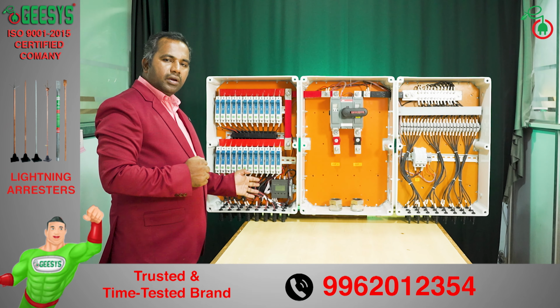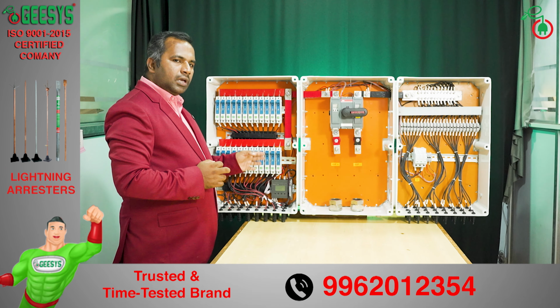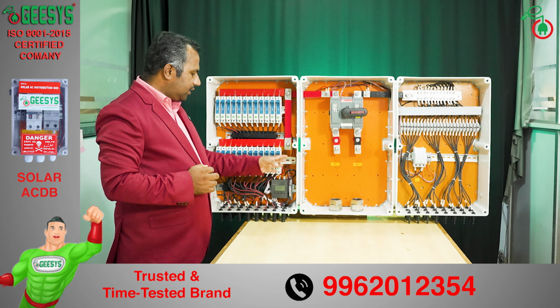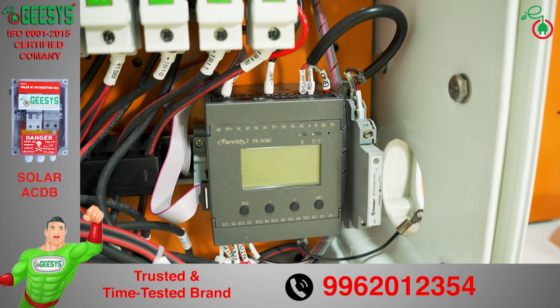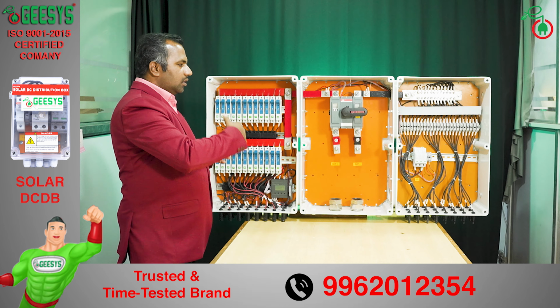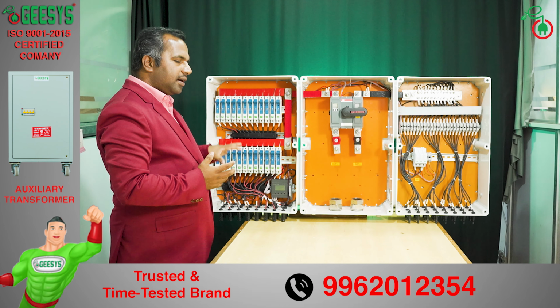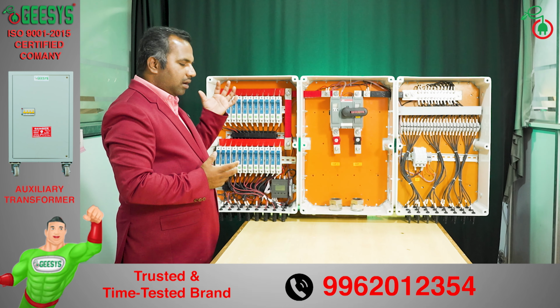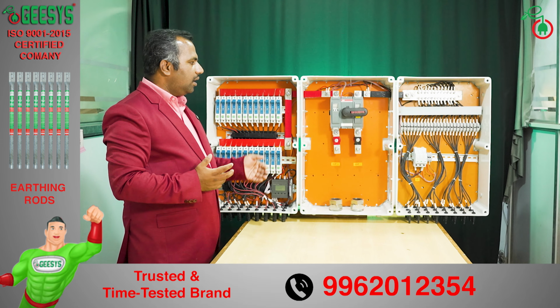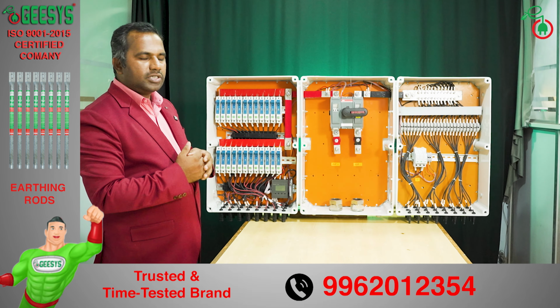The string monitoring unit will give you RS485 data. The RS485 data will be connected to a data SPD, and the data SPD will safely transmit to your local SCADA system. In this box, we are monitoring individual string current, string power and string unit, and inside the box temperature and status of the switch, status of the SPDs.